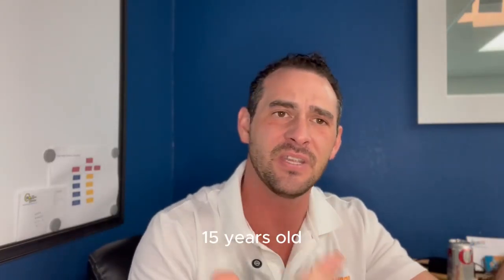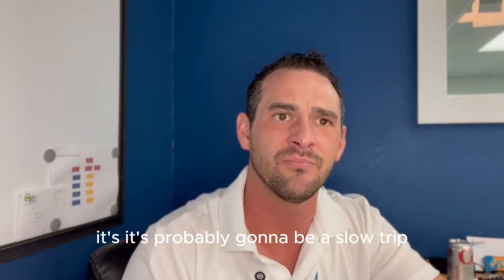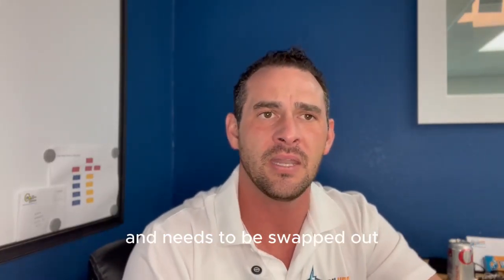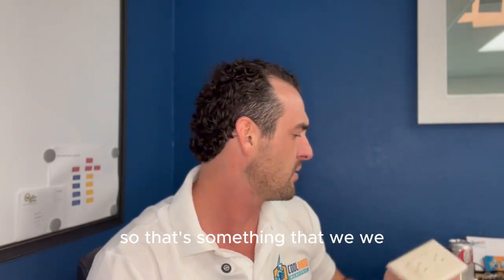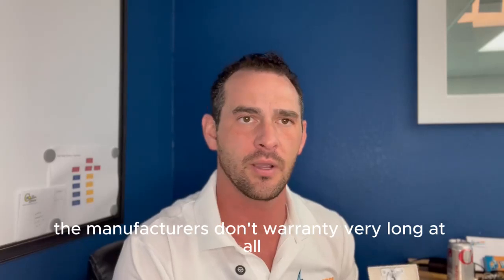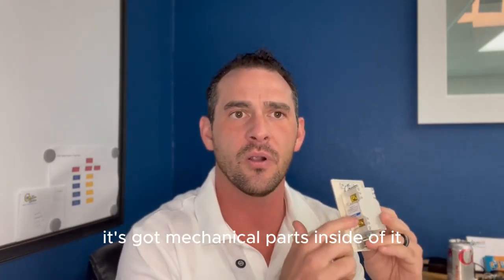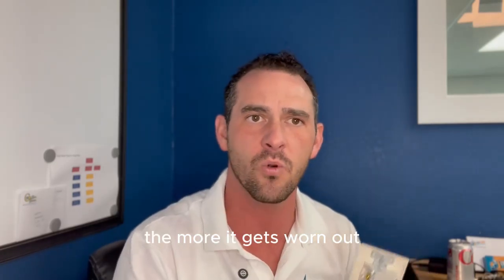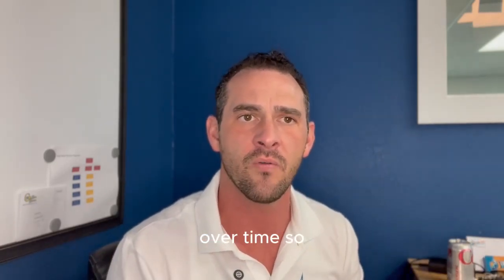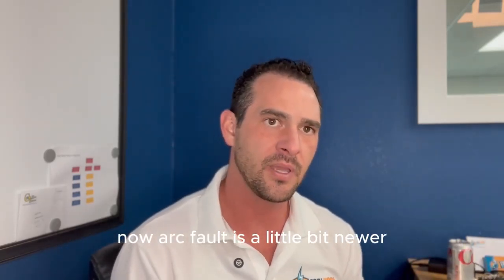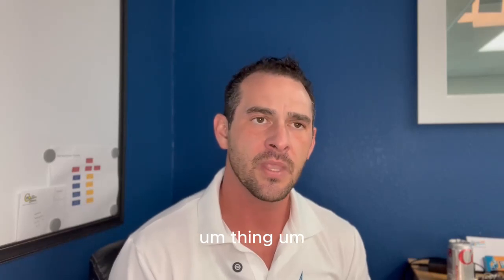If it's 10, 15 years old, it's probably going to be a slow trip and needs to be swapped out. So that's something that we change out quite often. The manufacturers don't warranty them very long at all, just because it's an electrical device. It's got mechanical parts inside of it. The more it's used, the more it gets worn out. It's going to go out over time. So that's with GFCIs. Now, arc faults are a little bit newer.